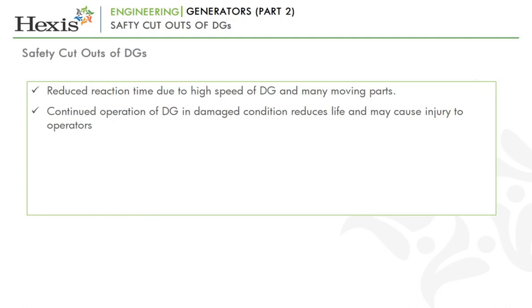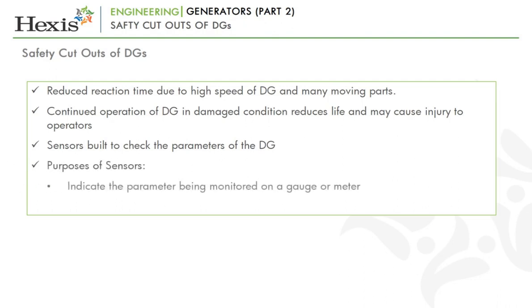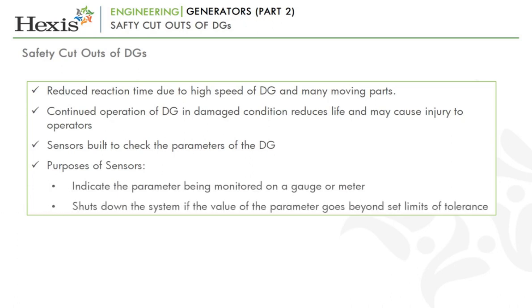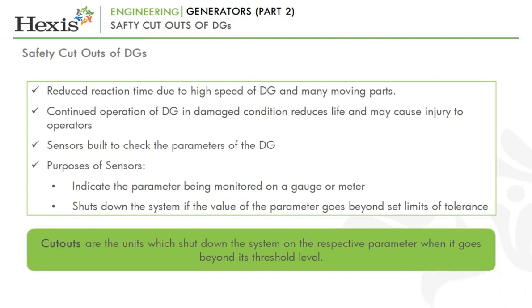For this reason, the manufacturers build in a lot of sensors to check the parameters of the DG. These sensors may be for temperature, pressure, differential pressure, and so on. These sensors are used for two basic purposes: to indicate the parameter being monitored on a gauge or meter and to shut down the system if the value of the parameter goes beyond set limits of tolerance. These units which shut down the system on the respective parameter going beyond the threshold levels are called cutouts. We will now learn what these are.